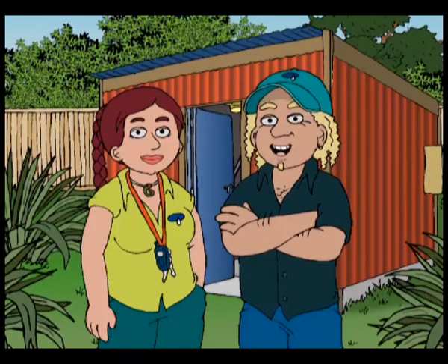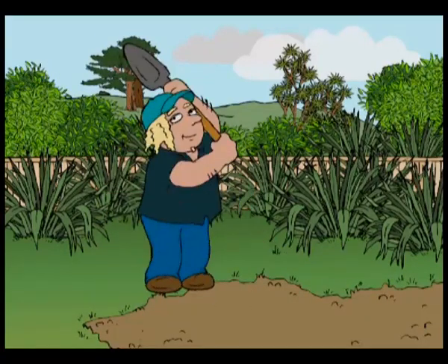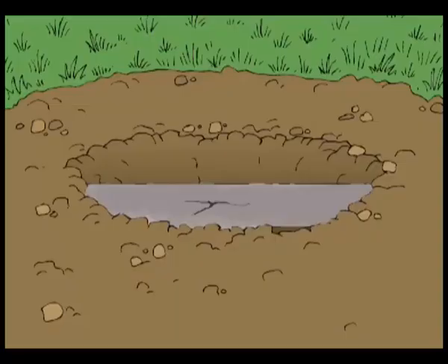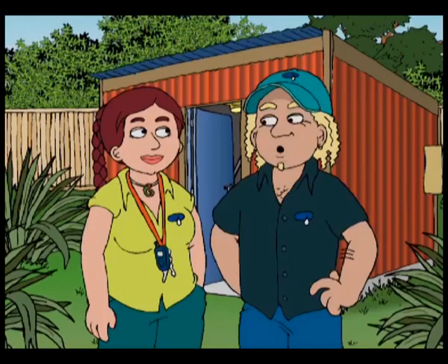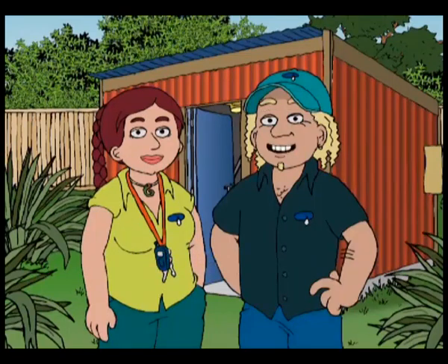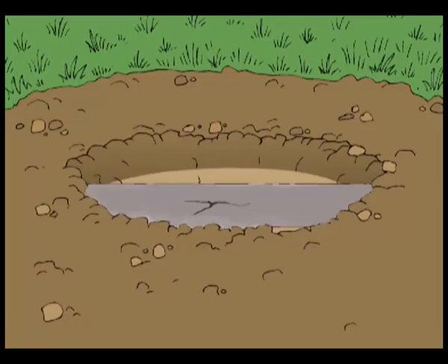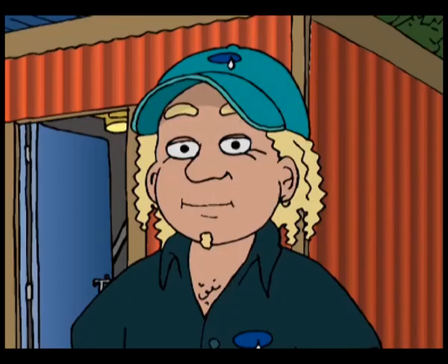Last year, one of our pipes burst, so we found out where it was leaking, dug it up with the intention of fixing it. Dug it up, exposed it, and left a hole around it so we could work on it. Now the leak meant that the hole we dug slowly filled up with water, but we thought to ourselves that at least the water that was coming out was clean. What we didn't figure on was that there was a slight drop in water pressure and some of the water in the hole got sucked back into the system, and that water wasn't clean anymore.